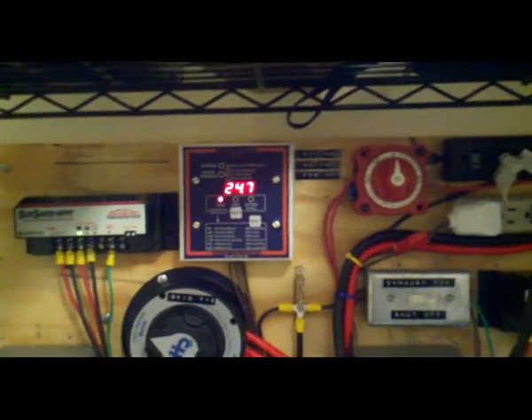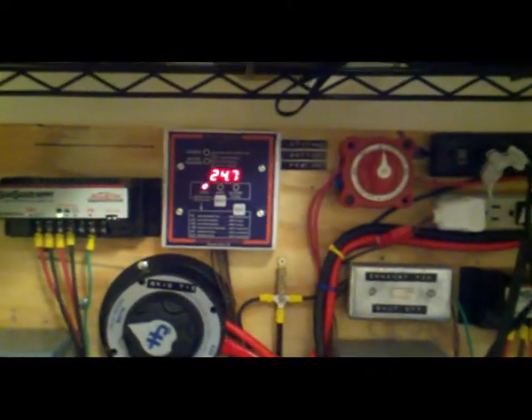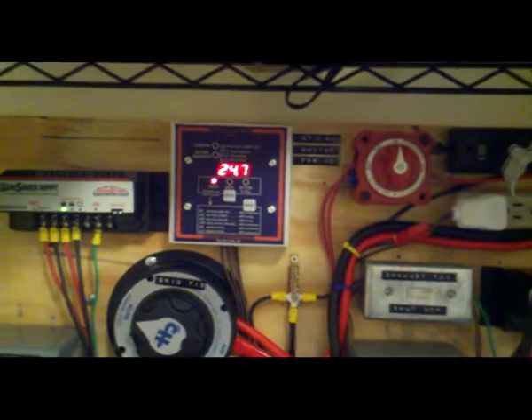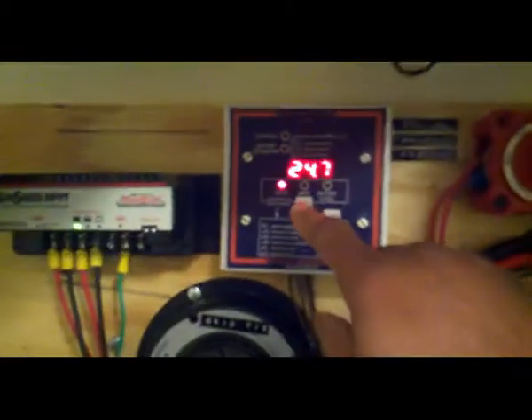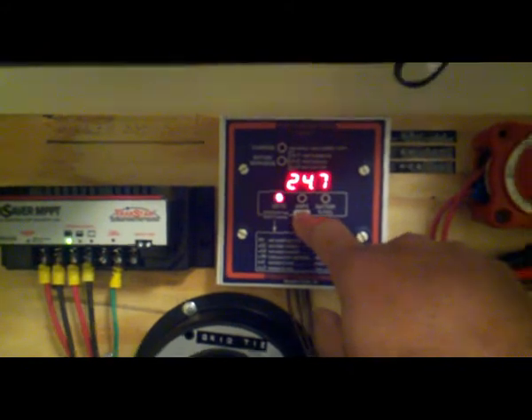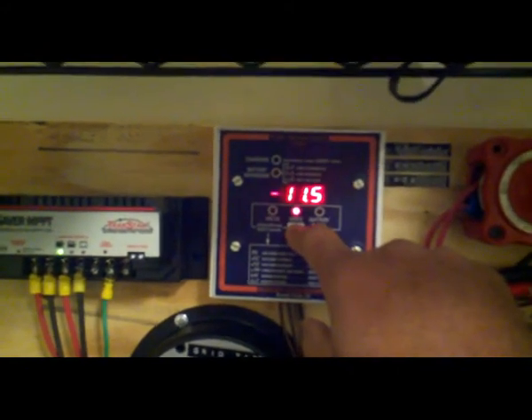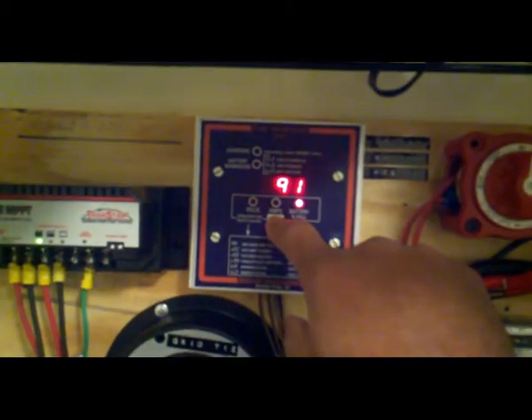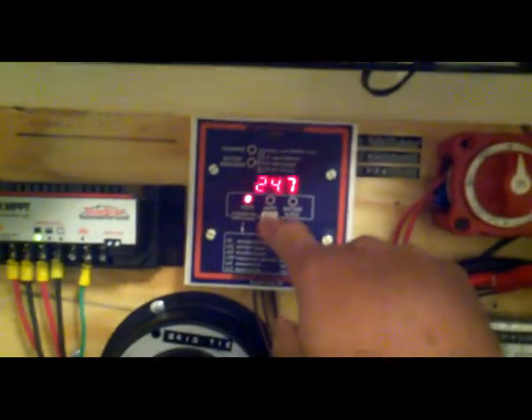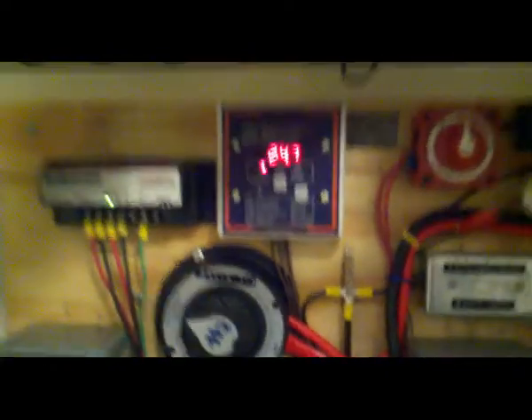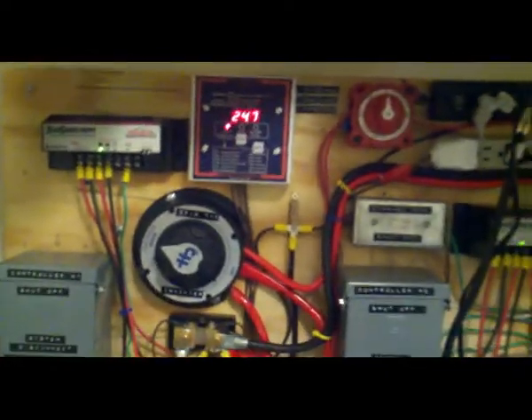Right now it's at 24.7 volts. It won't take them no time to bring it up to 25 and 26 volts easy. It's been running since early this morning, around 8 a.m. I got 11.5 amps coming out of the bank, and I'm at just 91%, which is fine. At 24.7 volts, I can live with that.